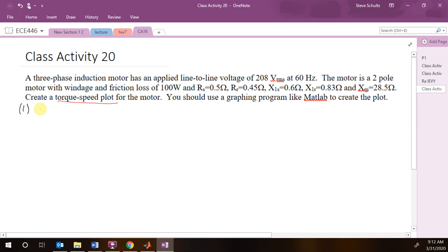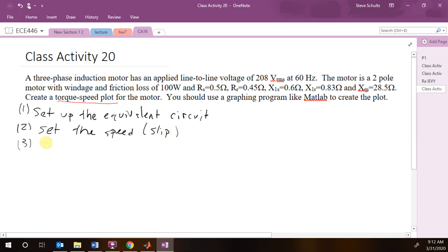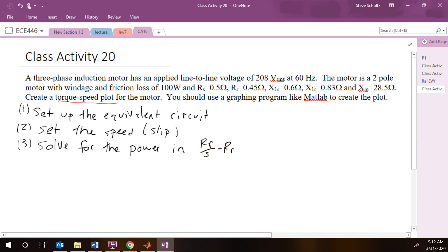Let's go through these steps again. Step one is we are going to set up the equivalent circuit. Step two, we are going to set the speed, meaning the slip. Step three, solve for the power in the resistance that models the mechanical power, which is the rotor resistance over s minus the rotor resistance. Step four, torque is equal to mechanical power divided by the speed.